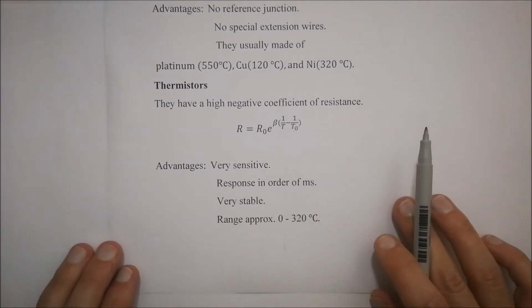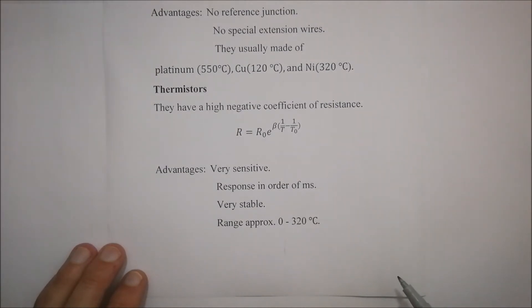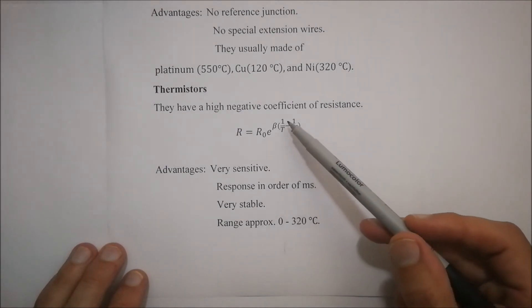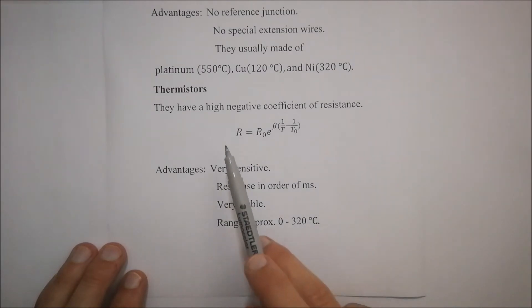Then we've got thermistors. They have a high negative coefficient of resistance. You'll actually see that the temperature over there is inverted in this exponential equation. So the resistance equal to the resistance at zero degrees Celsius, multiplied by e to the power of beta, multiplied by one over T minus one over the temperature at zero.